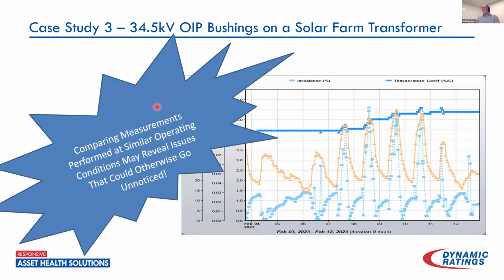So in this situation, to get to the bottom of what was happening, we had to take a look at measurements and compare them at similar operating conditions. We may have to do that same thing when it comes to partial discharge activity and things like that to identify what's happening. But bottom line, online monitoring makes this whole task easier, and it gives me the opportunity to identify these correlations.